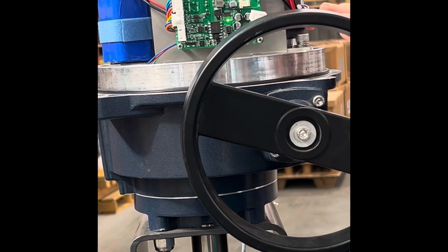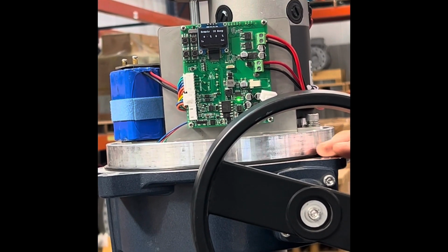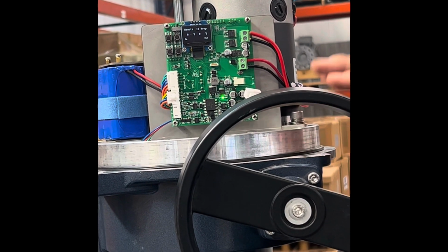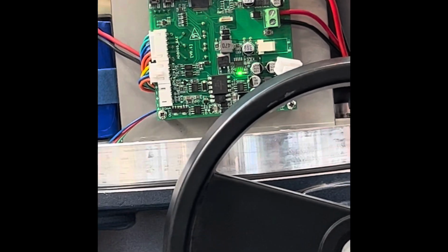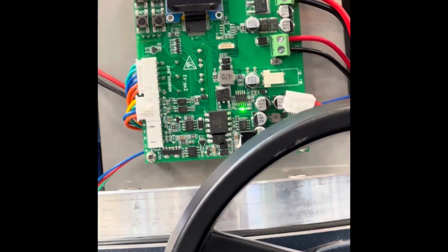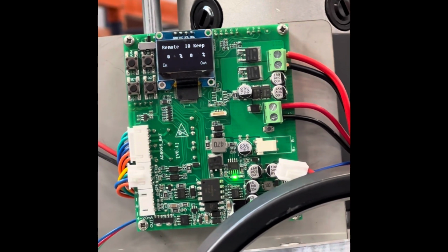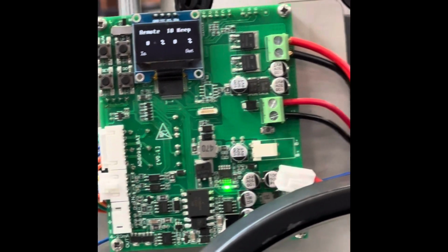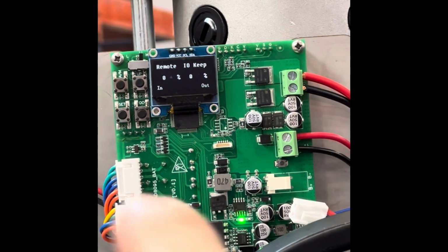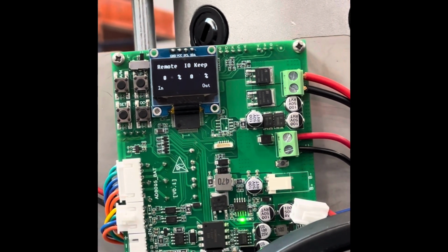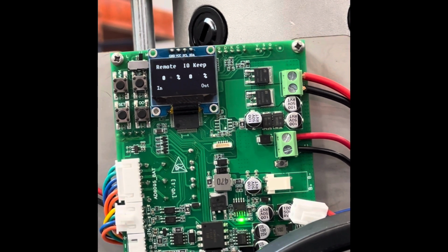I'm going to talk a little bit about the VTM 10S fast cycle actuator, the calibration, and changing from a keep signal, which means you have a dry contact, you give just a little touch of contact to the terminal block, and it's going to go either open or closed. So you can do a keep, you can do a pulse, or you can make that contact, and as long as you have that contact made, it's going to continue operating. When you remove the contact, it's going to stop.